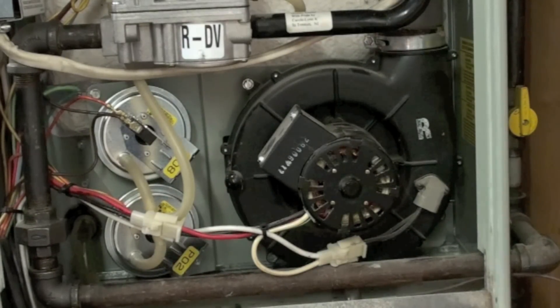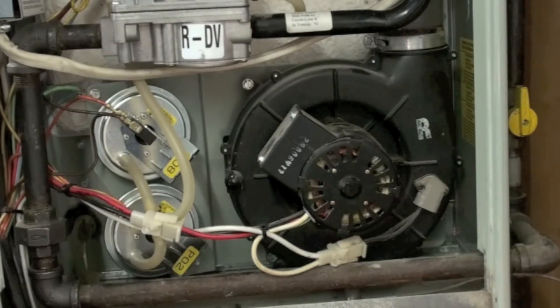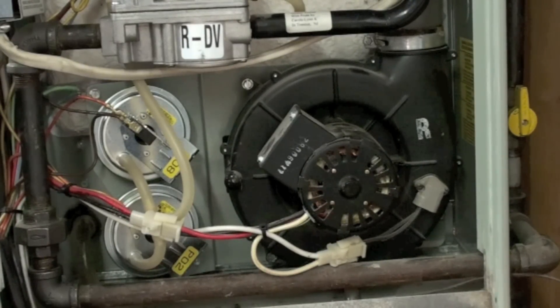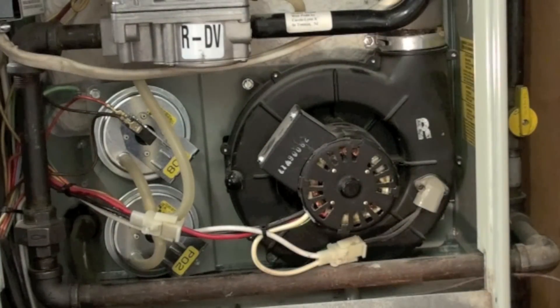Inducer may not be coming up to speed. I'd make sure I knew that was the problem before I took that thing off. That little bugger is expensive and it comes as one piece. Very seldom can you take one and replace a motor in it. I would not think that was it until I did a lot of research.